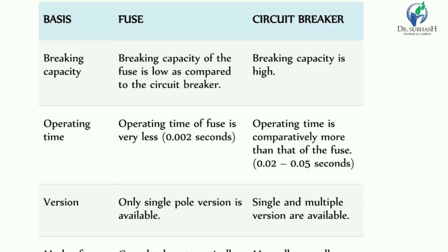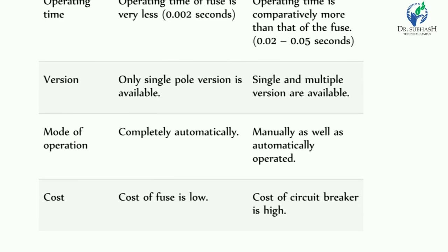The breaking capacity of a fuse is low as compared to a circuit breaker; the breaking capacity of a circuit breaker is higher. The operating time of a fuse is very low — 0.002 seconds — whereas the circuit breaker operating time is 0.02 to 0.05 seconds. Regarding poles: the fuse is only single pole, while the circuit breaker is available in single pole, double pole, and multiple pole versions. The mode of operation of a fuse is completely automatic, while the circuit breaker can operate both manually and automatically.